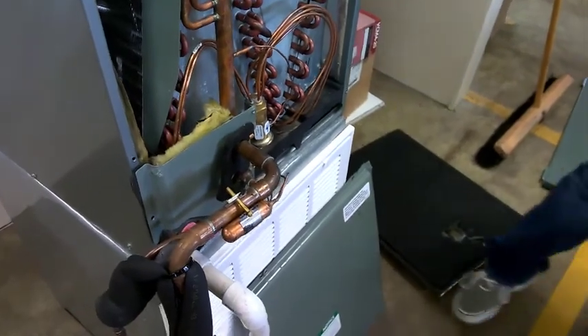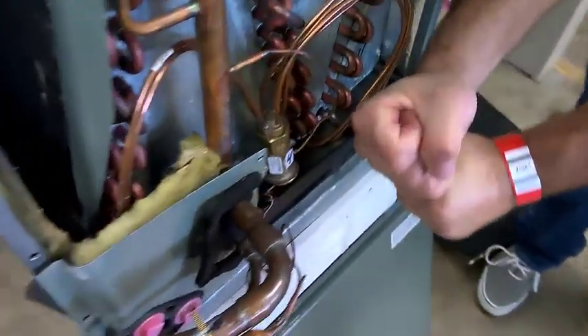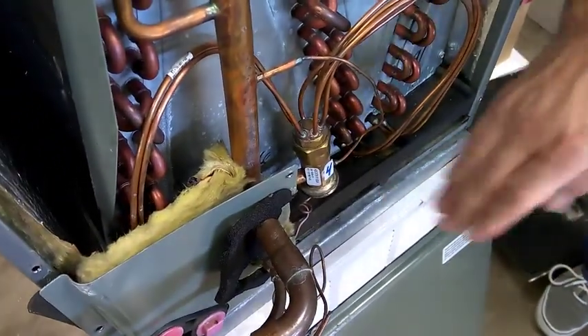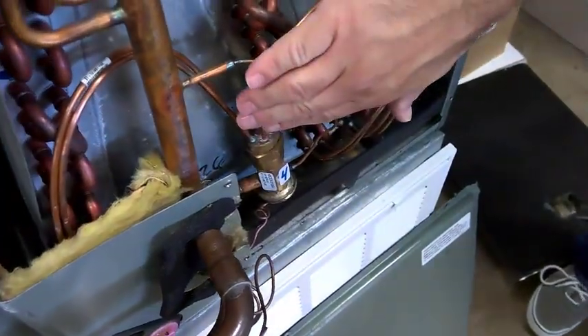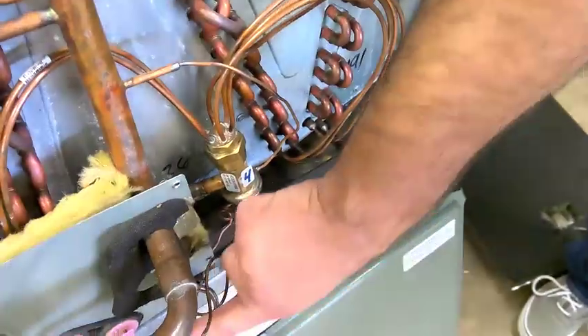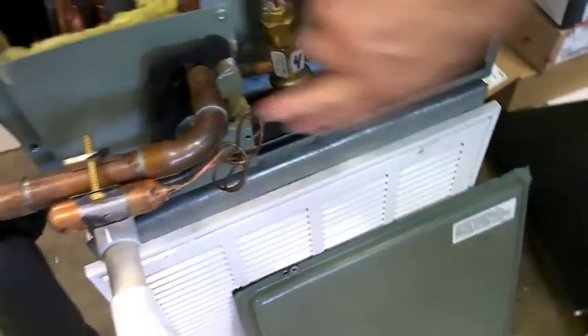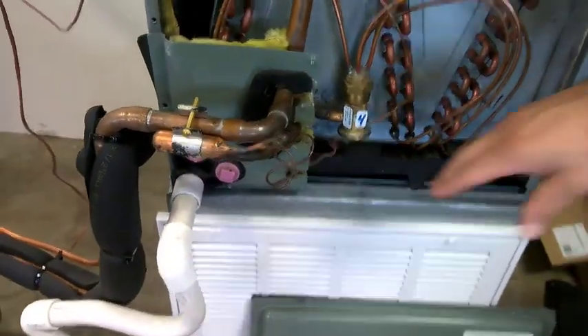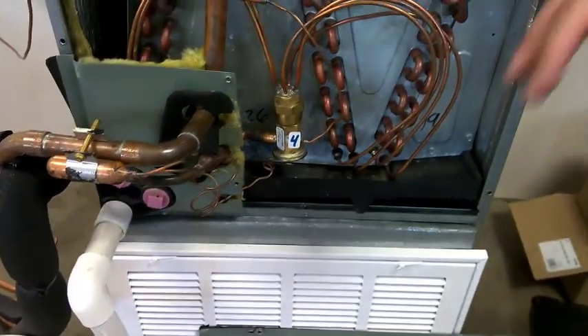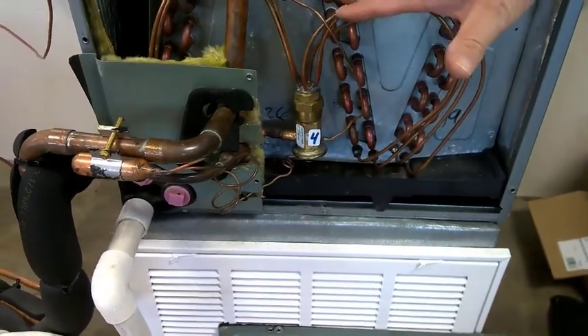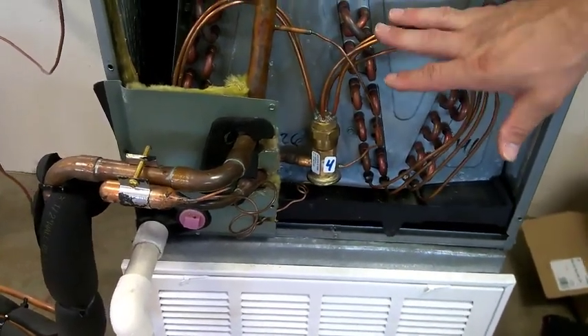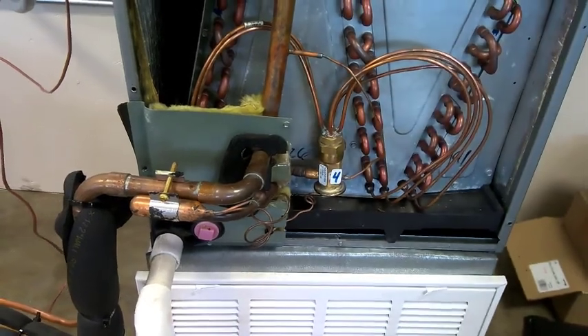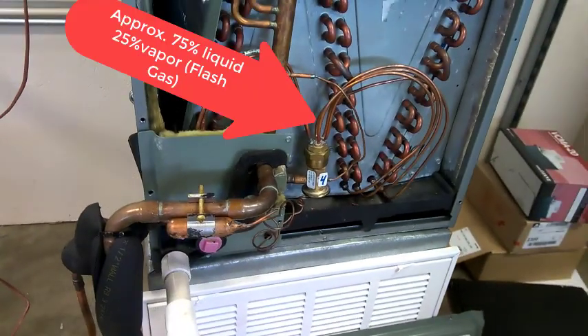With that compressor pumping, that TXV choking down that refrigerant, we're going to create a low pressure on this side of it. So that compressor is pushing to this point, increasing the pressure. Then it has to go through a tiny orifice, so it drops to a really, really low pressure. All right, once it does that, it becomes a cold refrigerant.